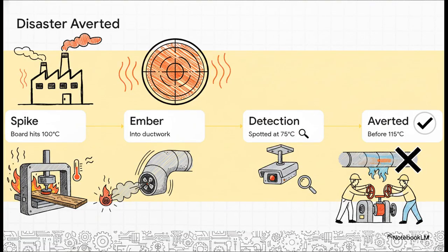This timeline perfectly captures how terrifyingly fast industrial fires can spread. Step 1. A board gets stuck on the planer, and it starts creating immense friction. Instantly, the thermal camera detects a rapid temperature spike to 100 degrees Celsius. Step 2.